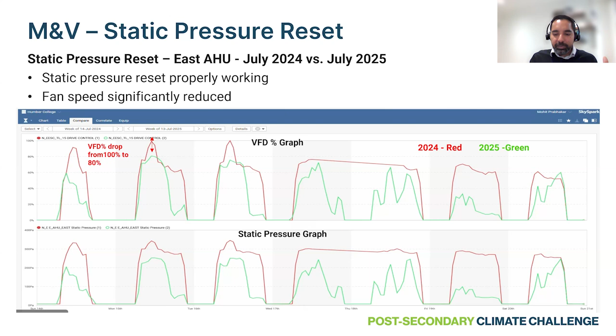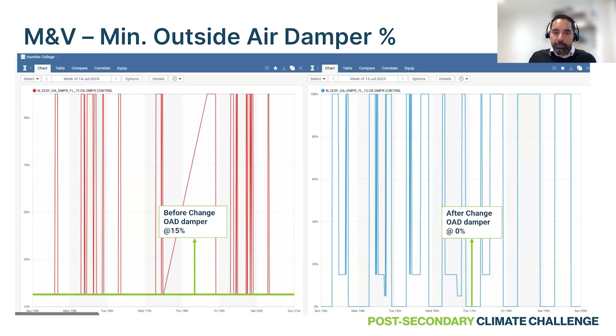Similarly, you can see the other measures before implementation. The outside air damper on this unit was open 15%, even when the unit was off. When this was identified, the damper position was changed to 0%, which avoided air leaking into the system during the unoccupied period. The humidification set point was again an easy fix. You look at all the humidification set points in your system, and this one was identified as a high set point, which was enabling the humidifiers all the time. The set point was changed, and as a result the humidification load decreased in that building.